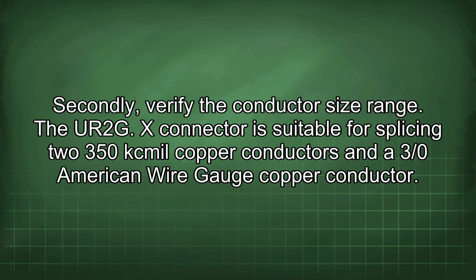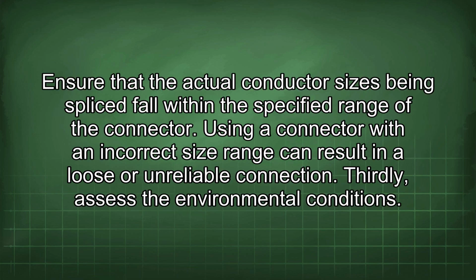Secondly, verify the conductor size range. The UR2G X connector is suitable for splicing two 350 kcmil copper conductors and a 3/0 American wire gauge copper conductor. Ensure that the actual conductor sizes being spliced fall within the specified range of the connector. Using a connector with an incorrect size range can result in a loose or unreliable connection.